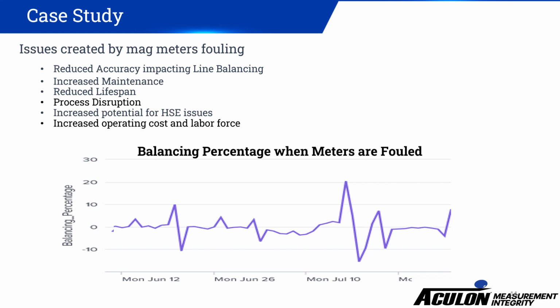There are issues related to over-torquing, as most operators are not aware of the torquing requirements for a meter. If it's on a flange of 150 or 300 series, they do not often understand that the meter torquing is less. And then you also have just overall damage to electrical equipment related to the meter as it is rolled out and then put back into service. Or if it's hard piped, you have the headache of having someone come out and unwire it so the meter can be rolled out.